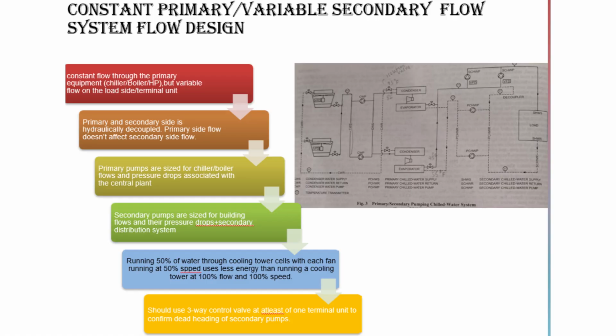on the primary side. Primary pumps are dedicated to the central plant. They are sized for the equipment flow requirements and the pressure drop through the chillers or boilers. Secondary pumps, on the other hand, are sized for the building distribution system. These pumps operate with variable frequency drives, adjusting their speed to match the demand from the terminal units such as air handling units, fan coils, and chilled water coils.